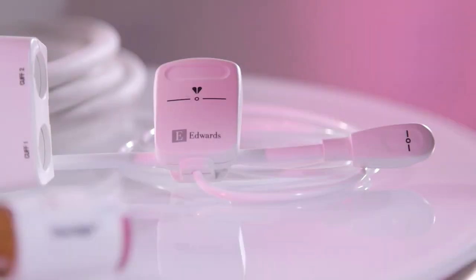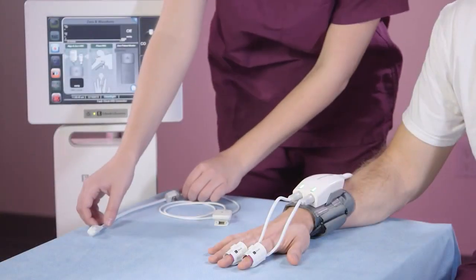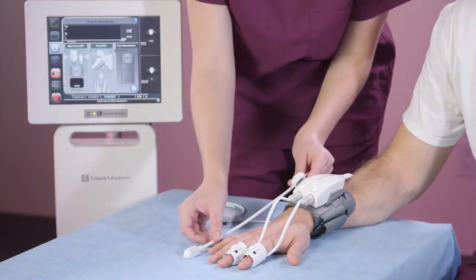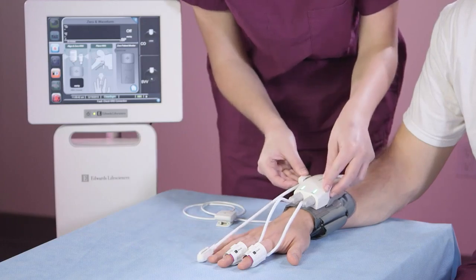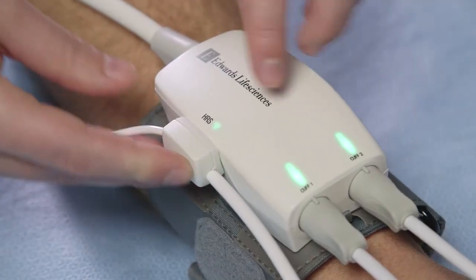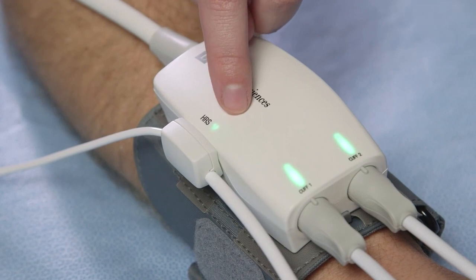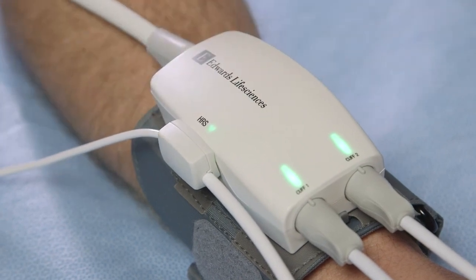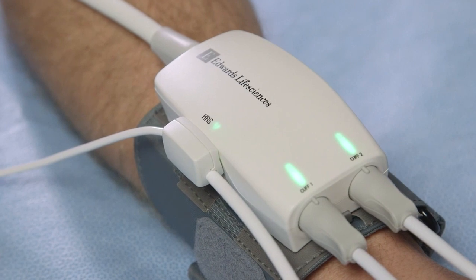The next component to be connected is the HRS. Connect the HRS to its respective port on the pressure controller. When it is properly connected, a green heart illuminates next to the HRS. If the heart is orange, the HRS has either expired and needs to be replaced or is a non-Edwards HRS. Note that this step must be complete before zeroing the HRS.